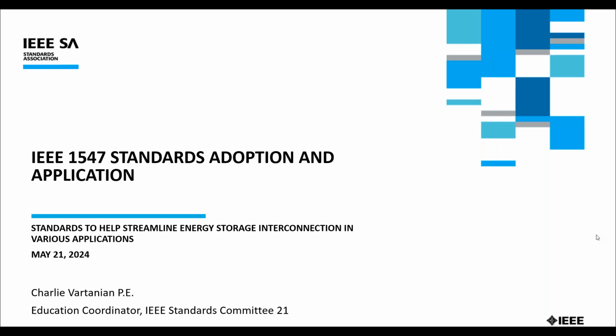Great news for the industry is 1547 has been thoroughly evaluated and applies as a technical basis for interconnection performance. The benefit is we don't have to create technology or project specific standards, as these baseline requirements are well spelled out. Same thing with 2800 at transmission, which was written even more intentionally as a 4-quadrant device or resource standard, so energy storage is covered by 2800.